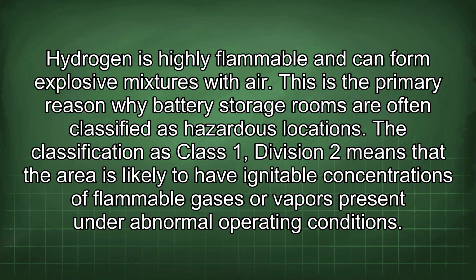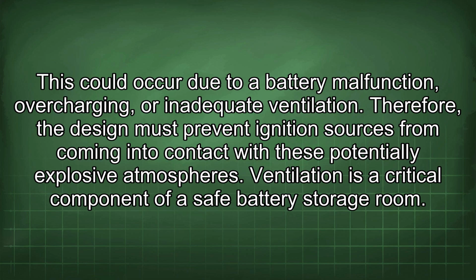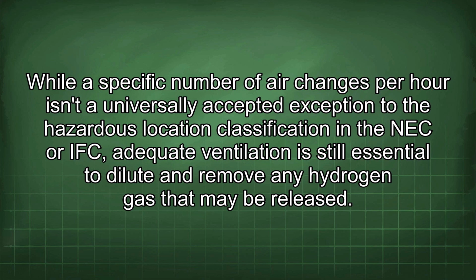The classification as Class 1, Division 2 means that the area is likely to have ignitable concentrations of flammable gases or vapors present under abnormal operating conditions. This could occur due to a battery malfunction, overcharging, or inadequate ventilation. Therefore, the design must prevent ignition sources from coming into contact with these potentially explosive atmospheres. Ventilation is a critical component of a safe battery storage room. While a specific number of air changes per hour isn't a universally accepted exception to the hazardous location classification in the NEC or IFC, adequate ventilation is still essential to dilute and remove any hydrogen gas that may be released.